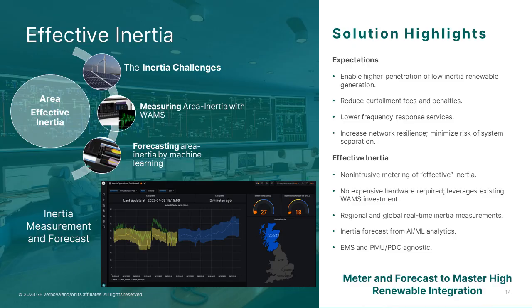We also realized that as we have more distributed generation on the grid, the concept that there's only one inertia for the grid is no longer true. We are seeing these pockets of inertia on the system. And that's why we use the word area effective inertia, because we can look at inertia in different regions of the system. So in the case of Great Britain, we have the system divided into 4 different regions, and we are measuring the inertia in each one of the 4 different regions.